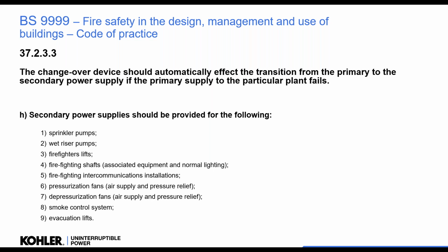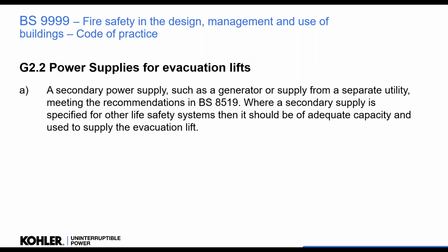All right, so it does say it shall have a changeover device to automatically transition between the normal mains and the secondary power supply, and it should be provided for sprinkler pumps, riser pumps, lifts, smoke extract, all those things. Okay, now G2.2 of this regulation says power supplies for lifts. Again, a secondary power supply such as a generator or supplied from a separate utility, meeting the recommendations in BS 8519, where a secondary supply is specified for other life safety systems, and it should be of adequate capacity and used to supply the evacuation lift.